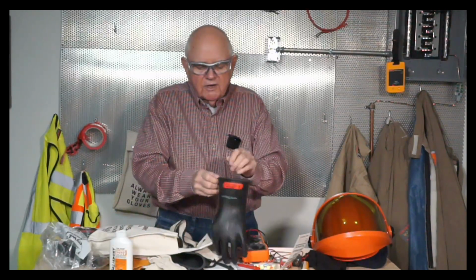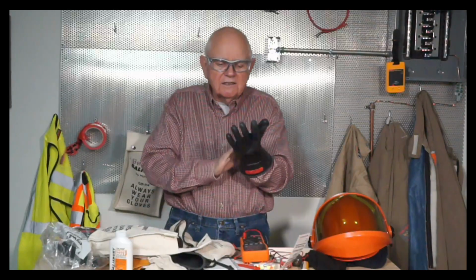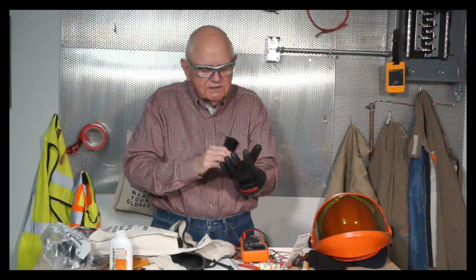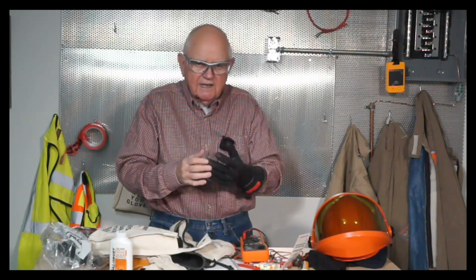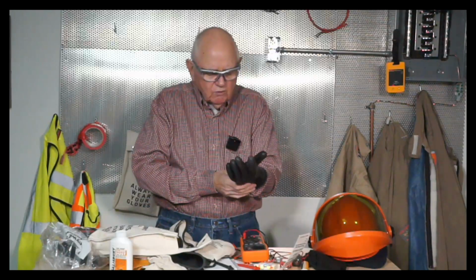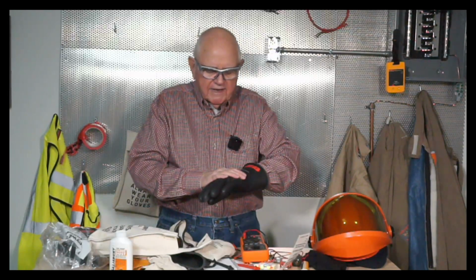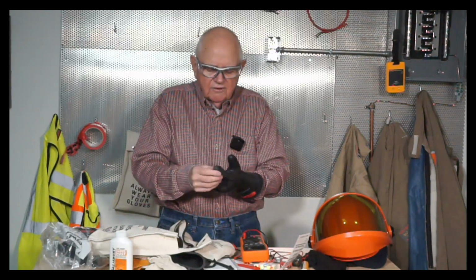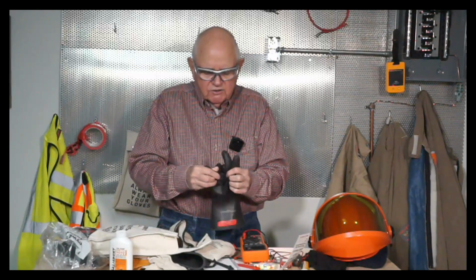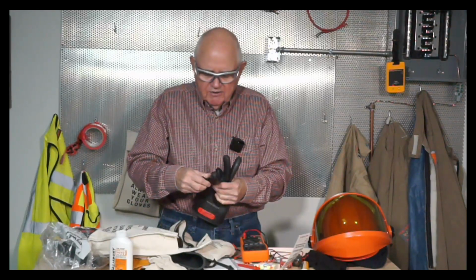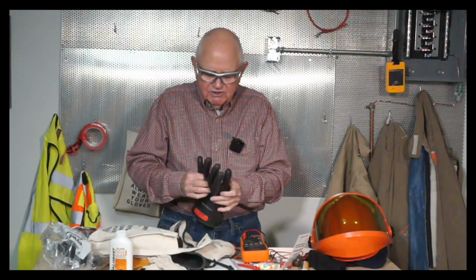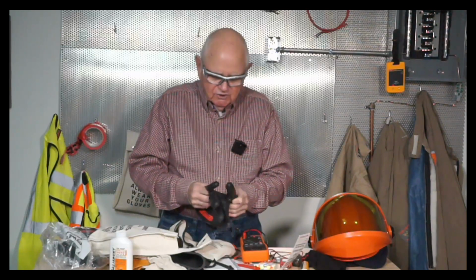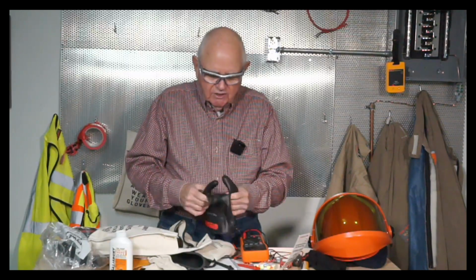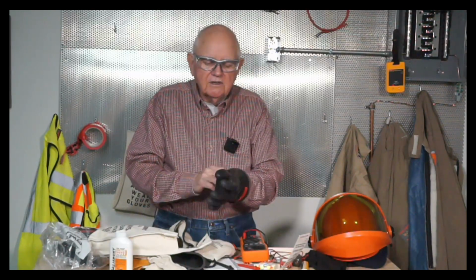Now, I go through and I'm going to put the glove on my hand. I'm going to inspect it. I'm going to look it over, look for any signs of deterioration, grease, oil, anything like that. Go to the manufacturer. If you need to wash your glove and clean it, they'll tell you how to do that. And so I inspect the glove. I'm going to take it off. I'm going to pull the fingers apart. I'm going to stretch the rubber in different directions. Make sure I don't see any cracking, what we would call ozone checking. No splits, no holes.